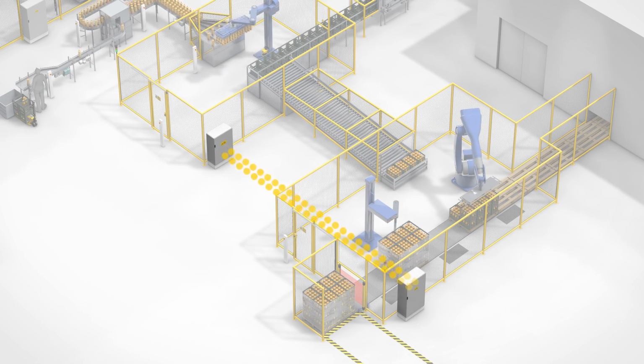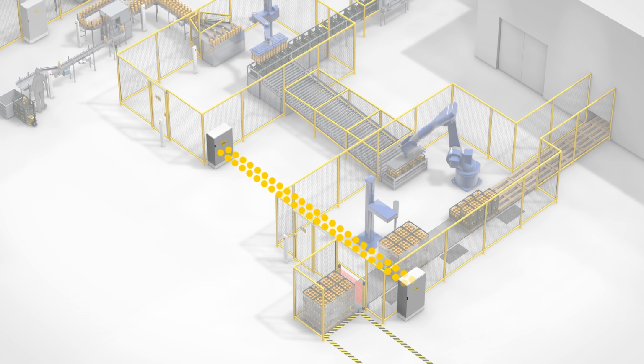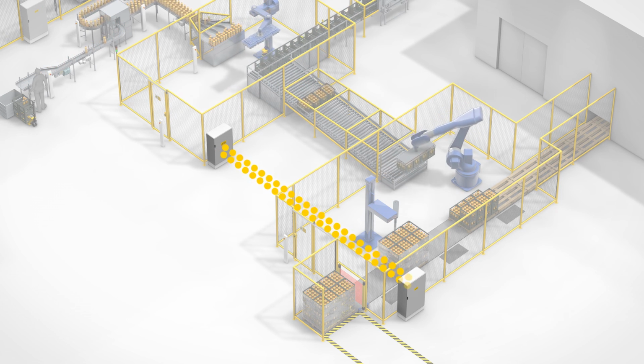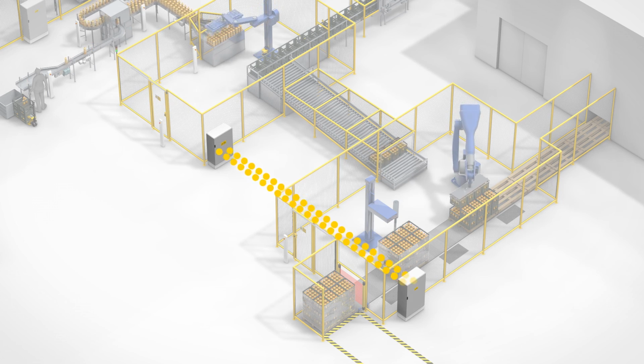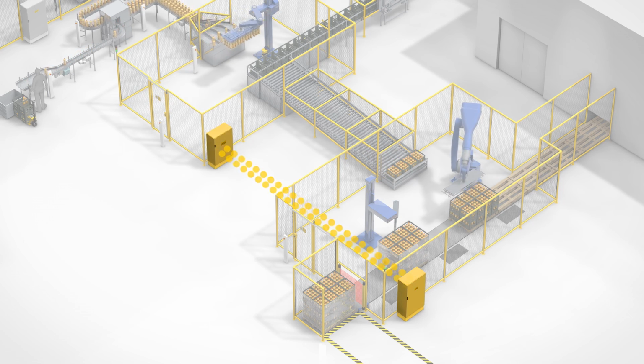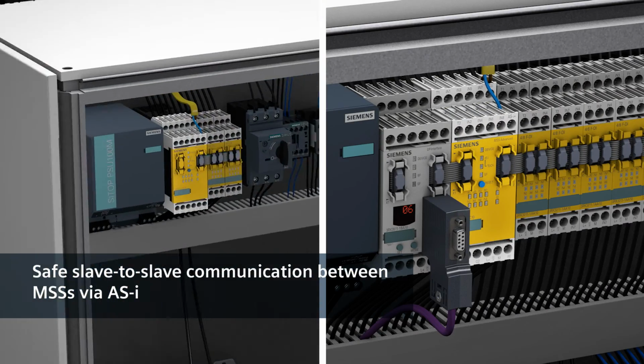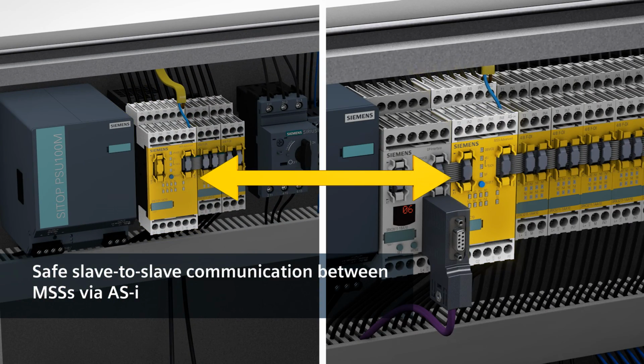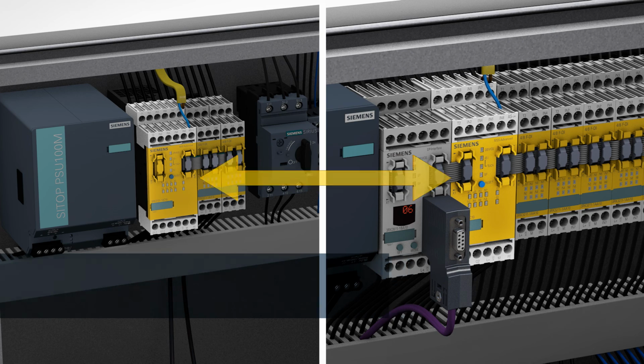But safe data exchange also has to take place between the two safety cells. If one safely shuts down, the other one has to shut down too. Both modular safety systems exchange information via ASI-Safe for this purpose. This type of communication is known as slave-to-slave communication.